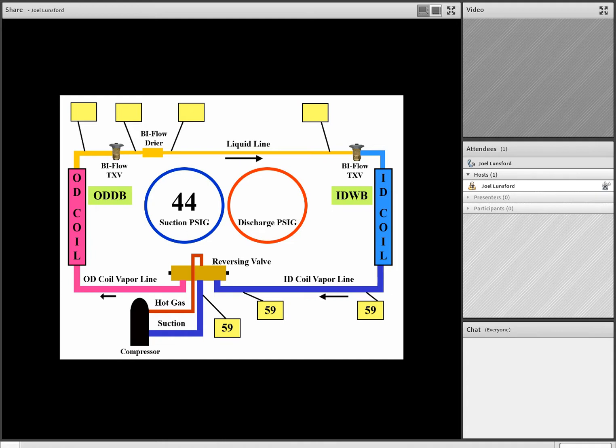And so remember, team, we said that if the superheat is high on the cold coil, the coil is starved. If the superheat is low, if it's a low number, the coil is flooded. And normal is about 10 to 15. But in our example, we see that we have over 30 degrees of superheat. 10 to 15 is normal, so the number is high. We have a high superheat number. That means the indoor coil in this example, in the cooling mode of operation, is starved for whatever reason. Now, team, we'll find out what some of those reasons are later. This is just strictly superheat practice right now to make sure everybody understands how superheat will help us find the condition, flooded, starved, or normal, of the cold coil.